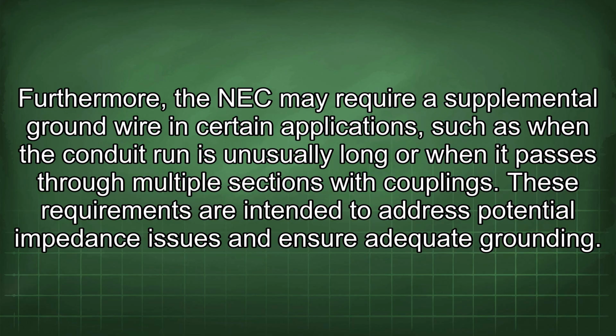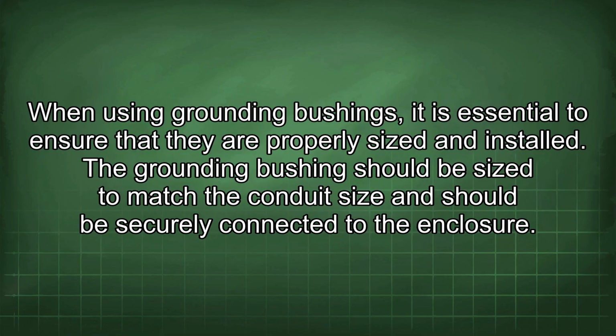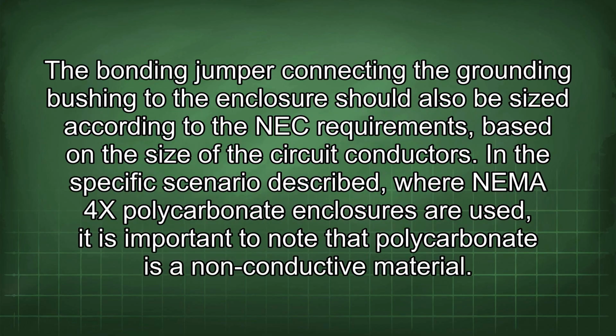Furthermore, the NEC may require a supplemental ground wire in certain applications, such as when the conduit run is unusually long or when it passes through multiple sections with couplings. These requirements are intended to address potential impedance issues and ensure adequate grounding. When using grounding bushings, it is essential to ensure that they are properly sized and installed. The grounding bushing should be sized to match the conduit size and should be securely connected to the enclosure. The bonding jumper connecting the grounding bushing to the enclosure should also be sized according to the NEC requirements based on the size of the circuit conductors.